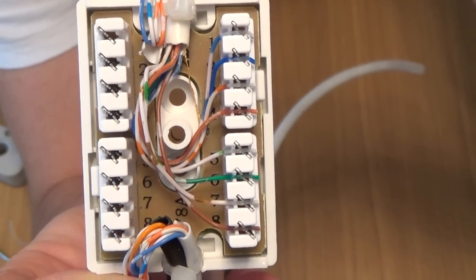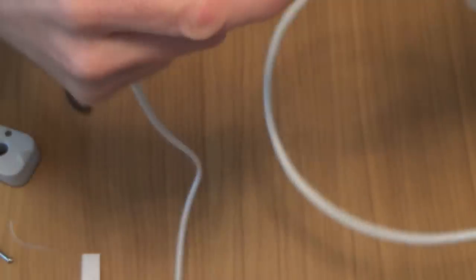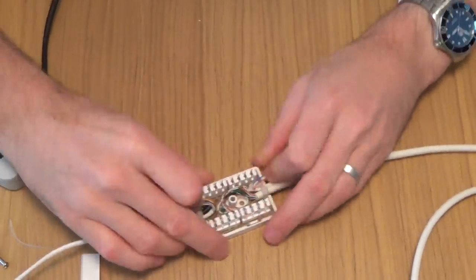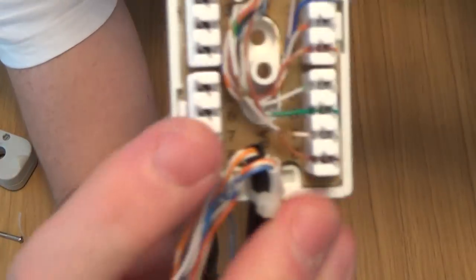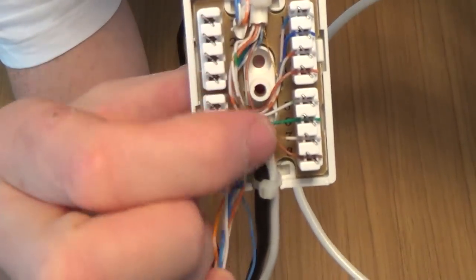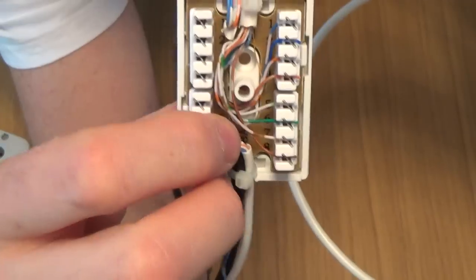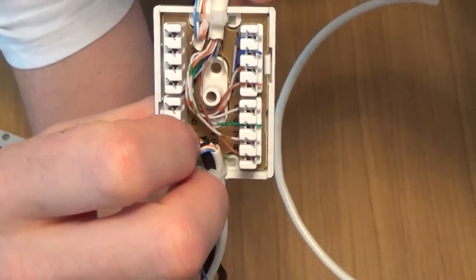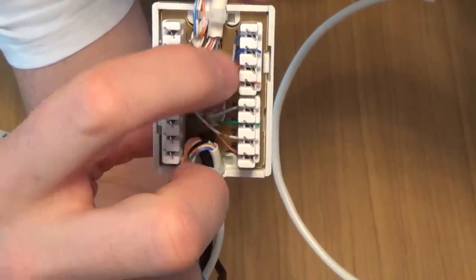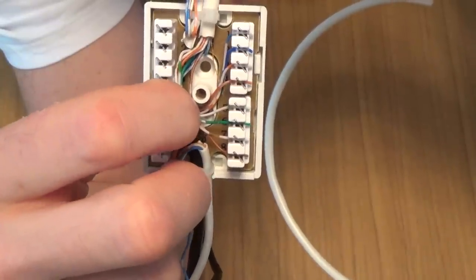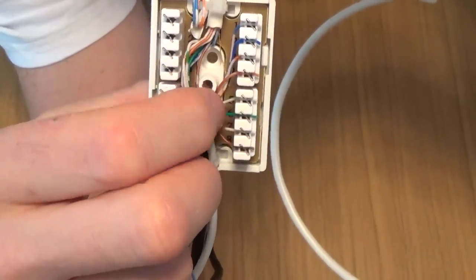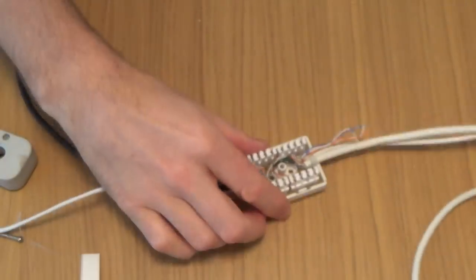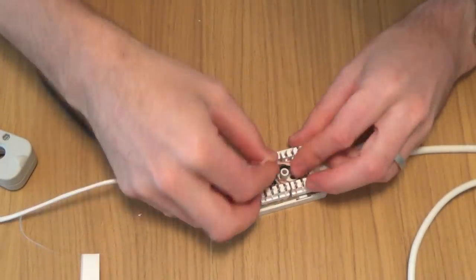Now we're just going to copy all the other cables onto that. So again, I'm going to keep working from the top here. And can you also see how I've routed it nicely away from the screw terminal? So it comes down and it goes around here and then back up. So you've got a little bit of slack to work with in the future, because if you come to this junction box again, you might have to pull the wires apart to do a bit of testing. If you do it too tight, then it's going to be hard for the next engineer to pull the wires out and then re-terminate them again. So always leave a nice little bit of slack, but not too much slack because you won't be able to get the lid on.